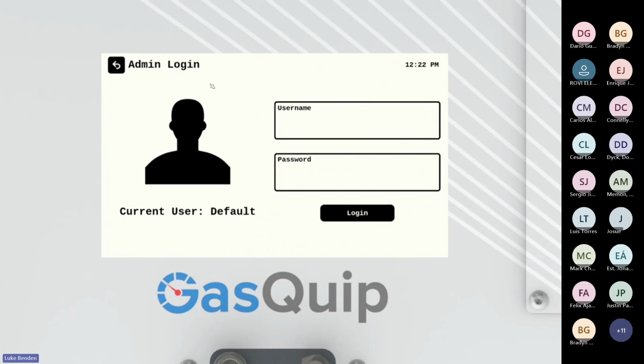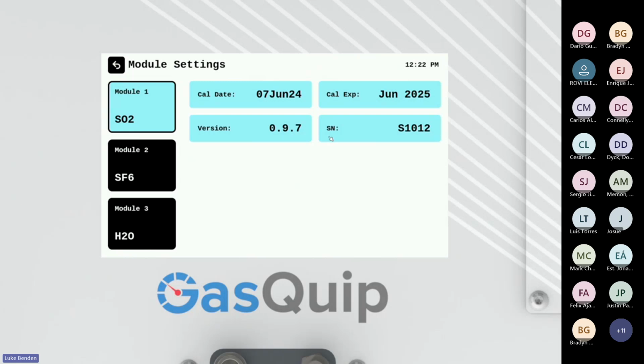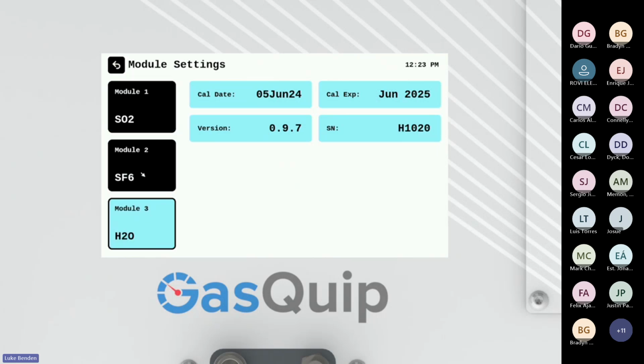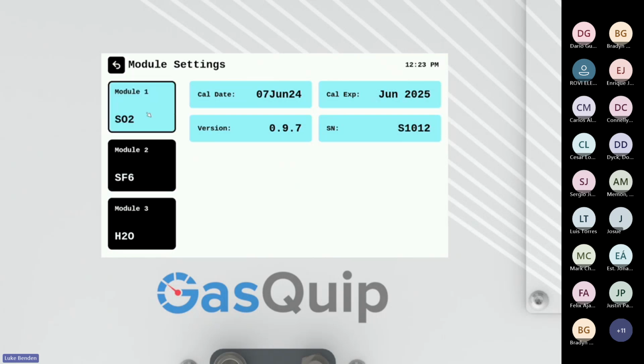So user settings, just for advanced settings for us to run diagnostics. Don't have to worry about that. Modules. So we have the sensor module data stored on each individual sensor, and you can have the information for the cal date, expiration date, the version, the serial number, and you can just click through the list of different sensor modules here. Like I said, as you remove and replace the sensor modules, this data is automatically auto-filled to this menu, so you can go in and see which sensor module might need to be calibrated and which one is still good.